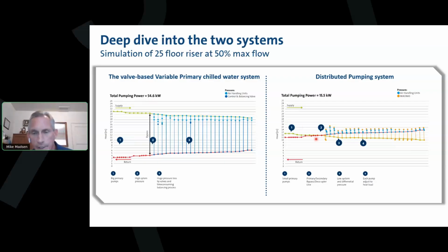If we look over to the distributed pumping approach, the first thing you'll notice is you have a much lower pressure profile. The primary pumps, all they need to do is keep the chillers happy and circulate water to and from the decoupler. Here's a decoupler, or the point of equal pressure. Here's my supply going out to the 25th floor. Here's my smart pump. I almost said my brand there. Here's my smart pump pressurizing, and then through the coil and then the return.